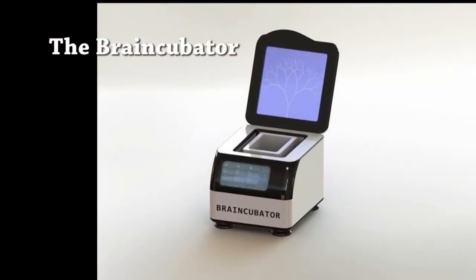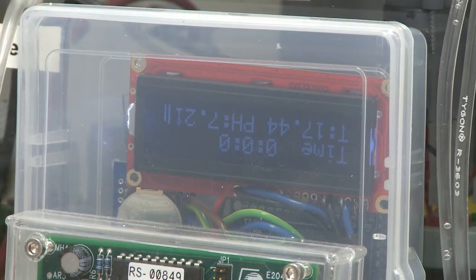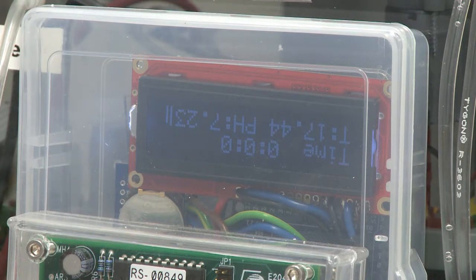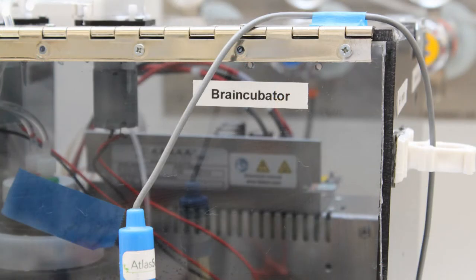The Braincubator is an incubation system for brain slices that is capable of extending their viability from 6 hours to more than 36 hours. The Braincubator is capable of monitoring and controlling the external environment, such as temperature, carbogen flow, and pH of the ACSF, and also keeping a sterile environment by reducing bacterial levels as it continuously passes the ACSF through a UVC filtration system.